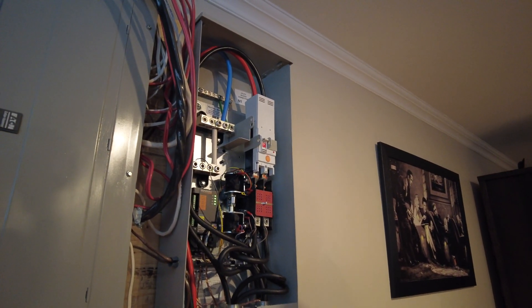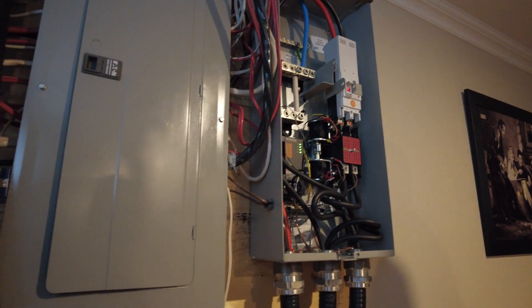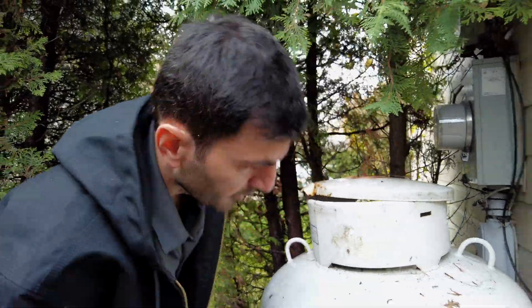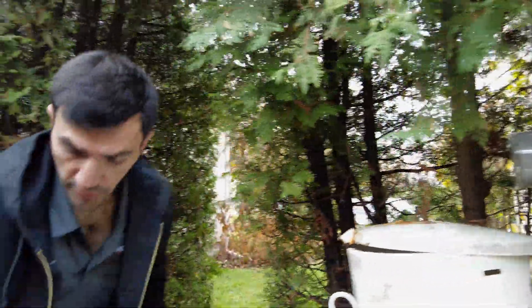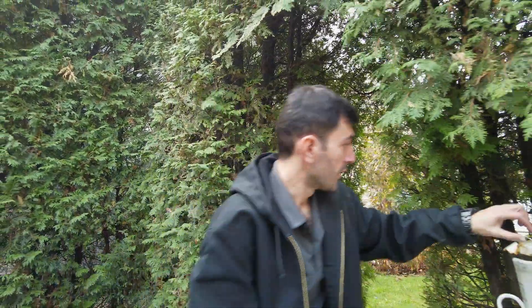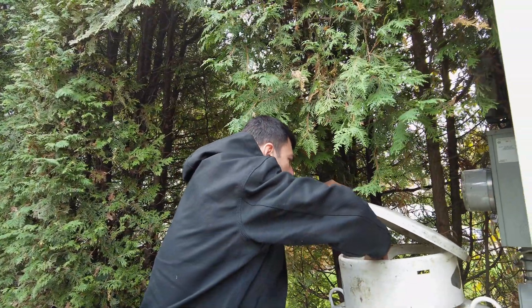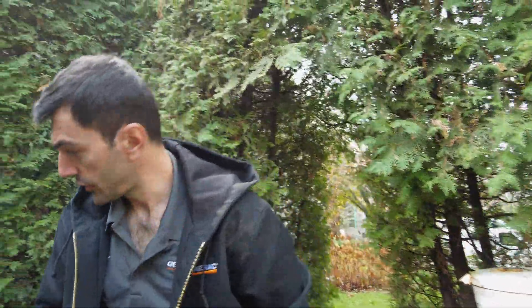If you want to make it correct, this whole thing has to come off to make it nice and clean. I smell gas here — yeah, it's leaking. The valve is not good and it's leaking, and it's right underneath the meter.